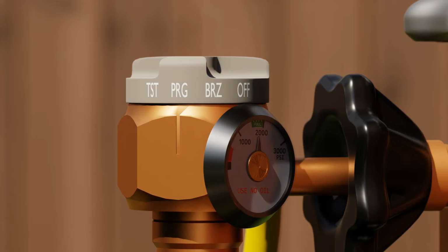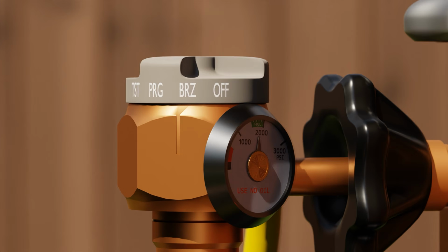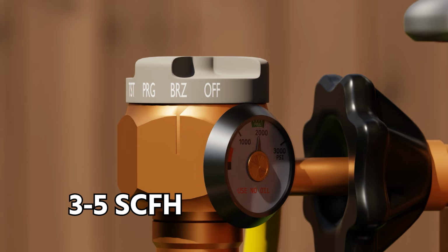Here we show the Western Enterprises nitrogen flow regulator that allows us to flow a very small amount of nitrogen through the tubing. If you don't have a special flow regulator like this, you can use a separate regulator on top of your regular nitrogen regulator that will flow at 3 to 5 SCFH of nitrogen during brazing.